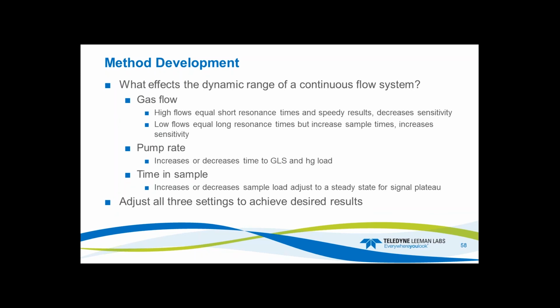Time in sample, same thing, increases or decreases the load, but you want to adjust it so it's a steady state for your method. So your signal plateau is flat, and your percent RSDs are good for the system. In most cases, the system will give you RSDs of less than 0.5%. I typically tell users that if it's less than 1%, you're fine. If it's less than 2%, you're okay. Once you get down into the sub PPT range, like 0.5 nanograms per liter, in that range your RSDs are going to go up a little bit by default.